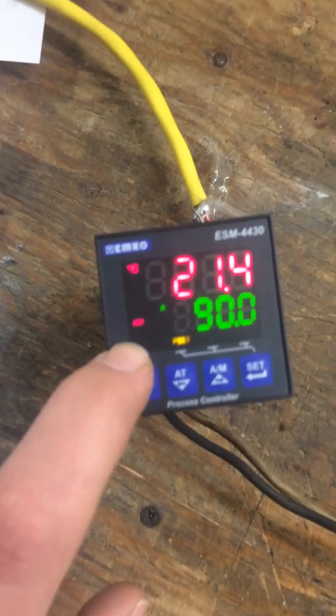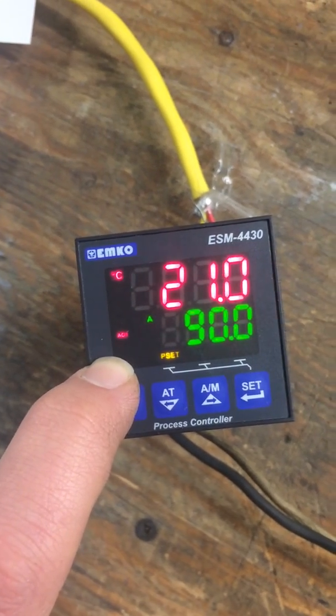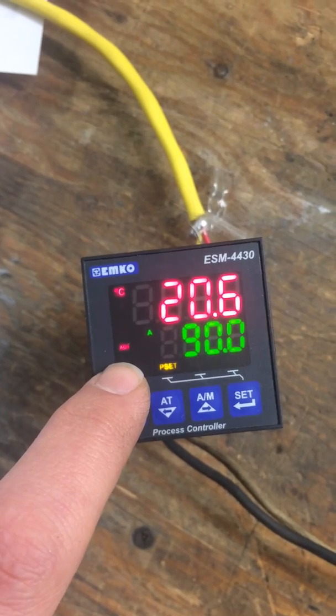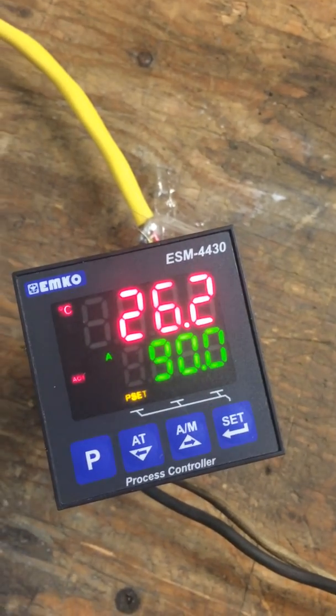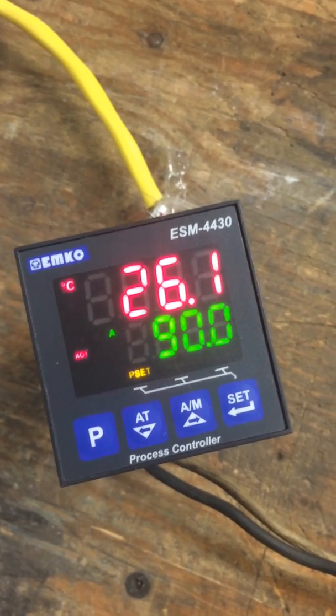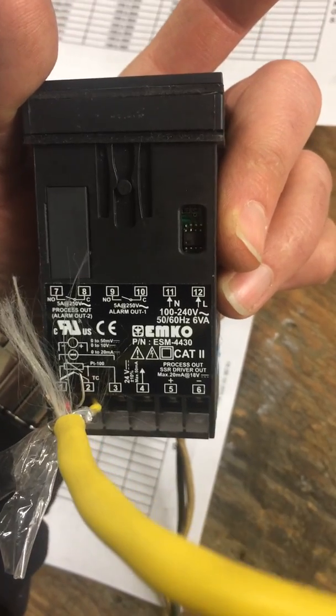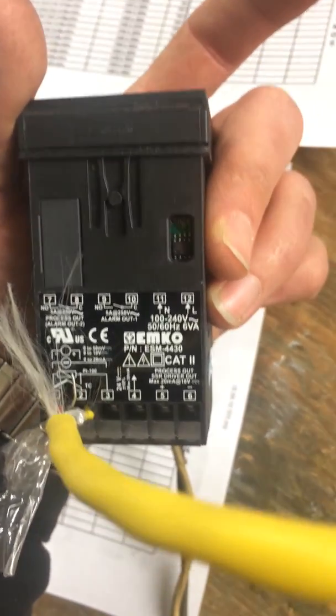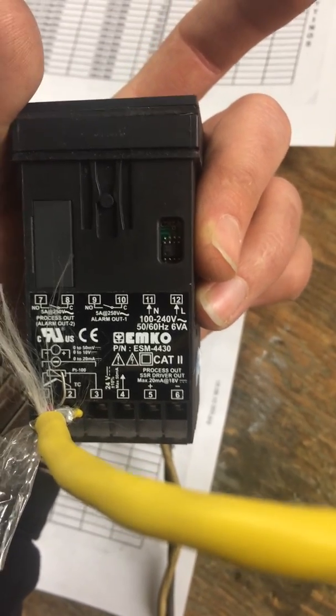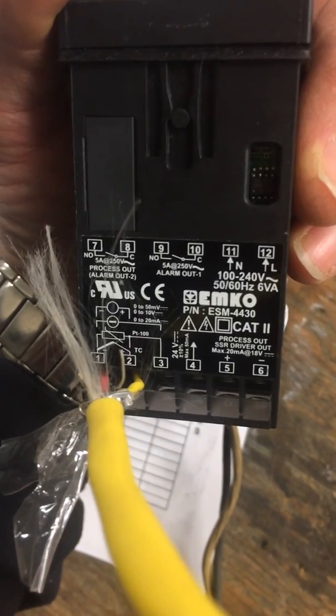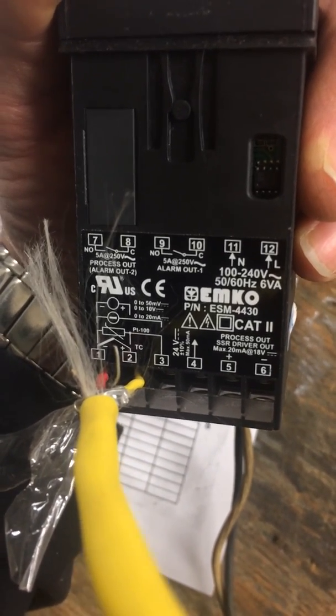What happens is, in the event — it says AO1. I have tripped this alarm by breaking the wire connection here — it's gone past 70°C. I put my finger on there and it's climbing temperature, so we know it's sensing correctly. I know ambient here is about 21°C. On the back side of this controller, we're going to be using numbers 9 and 10 for our alarm out 1. We use numbers 12 and 11 for our power input. And our sensor will actually be connected red as the negative to number 1, yellow to the positive as number 2.